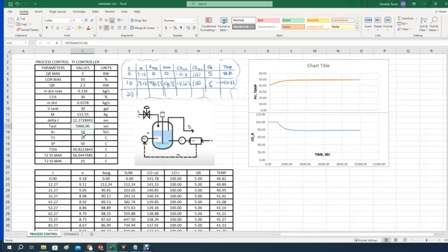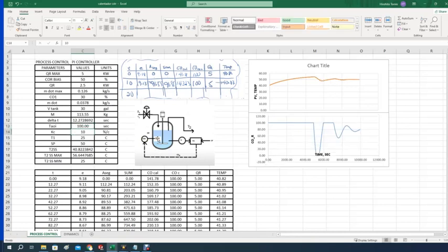I can put a small value. What is a small value here? I would say anything below 500. Let's say 500. I can start to see some oscillation, as last time. You can see that there's some oscillation. It went up, it went down, and then went up, and so the control operation oscillates as well. Now, if I use something even smaller than that, like 100, it will oscillate harder, and that's what is happening. You see, and you don't want that. It might cause some trouble in the control system.